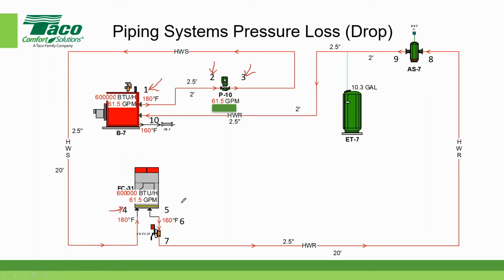And number 5 would be the outlet of the fan coil. Then I have a short piece of pipe from 5 to 6, and then the control valve, 6 to 7. Then from 7, I follow all the way along to point 8, and that's the inlet of the air and dirt separator. And then from point 8 to point 9 is the pressure drop across the air and dirt separator.